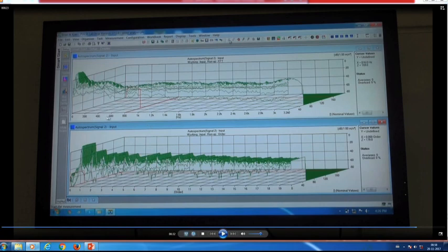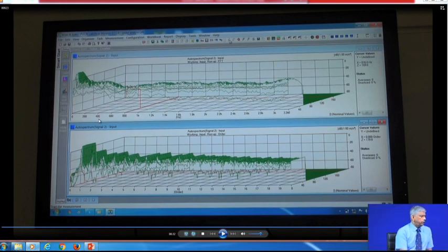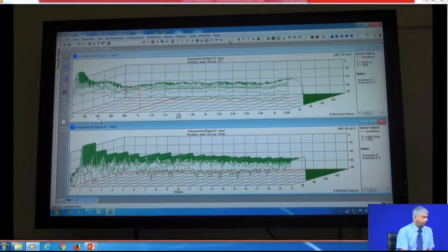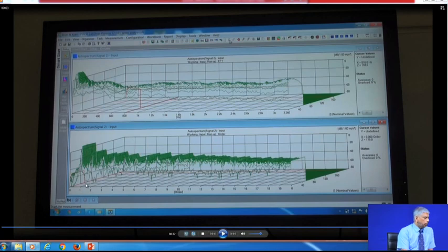One is the frequency domain plot, and this is in number of FFTs, or this could be in time domain as well, and the amplitude. So, in the process, what we did, we increased the speed and decreased the speed. In the frequency domain here, I am not able to see clearly any distinct frequencies, because the speed was changing, the frequency got smeared.